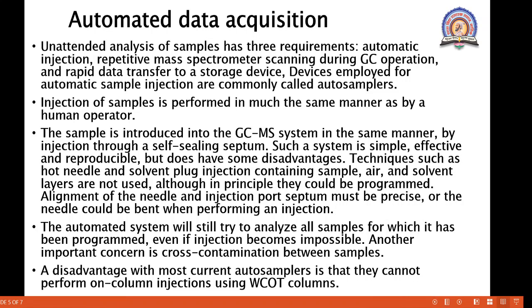The automated system will still try to analyze all the samples for which it has been programmed, even if injection becomes impossible. Another important concern is cross-contamination between samples. A disadvantage with most current auto samplers is that they cannot perform on-column injection using wall-coated columns.